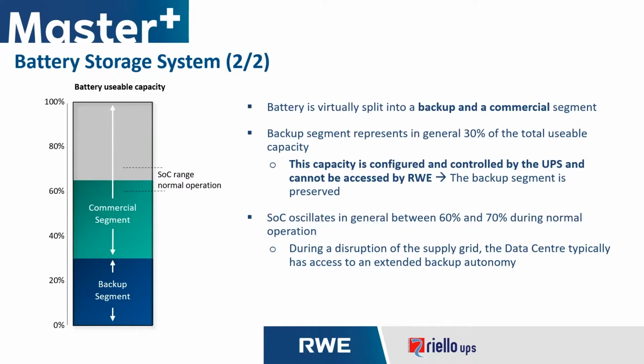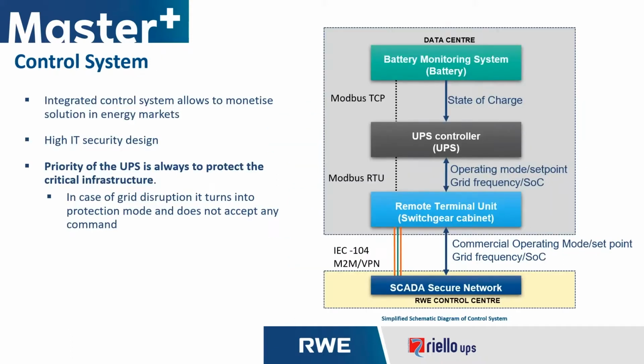Now obviously, should a main supply failure occur, then the data center will typically have access to the full and extended backup autonomy. The UPS controller and the battery monitoring system are connected to the RWE control center via a highly secure and integrated control network. Now this connection enables RWE to control and monitor the system and primarily monetize the solution within the energy markets.